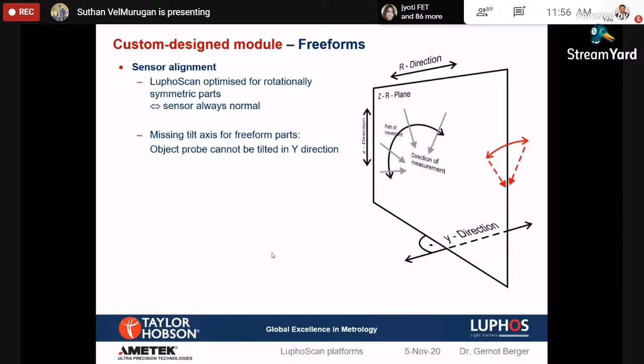can be measured by the standard probe. So the standard probe can measure, but if the customer needs any specific analysis for the free-form, we can generate only the software part of it, and the standard probe can be used. On the other side, if they have a free-form sample with more than plus minus 15 degree slope, my standard probe will have a limitation. So we have a special probe to cover the steep slope of plus minus 15 degrees. That can be added into the machine, and straight away they can measure it.